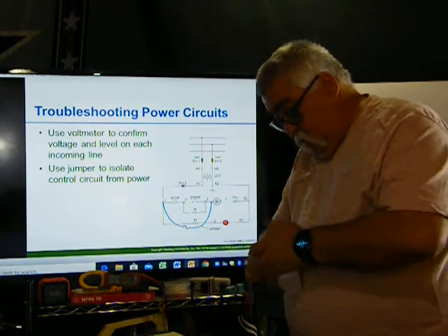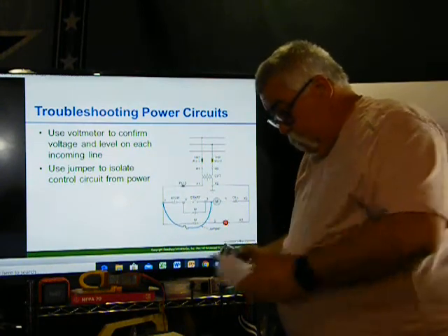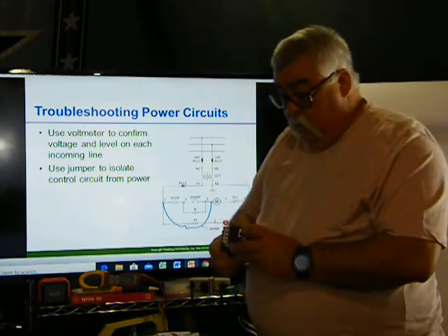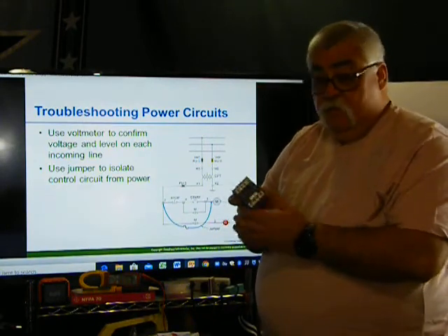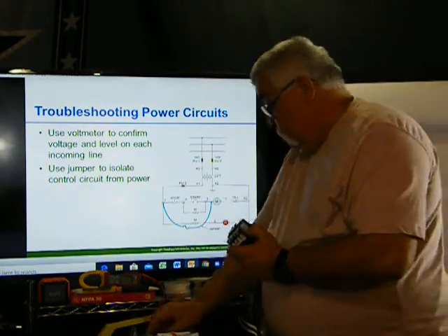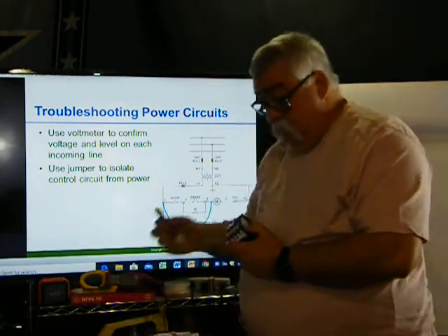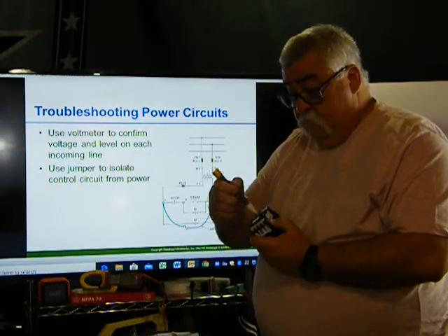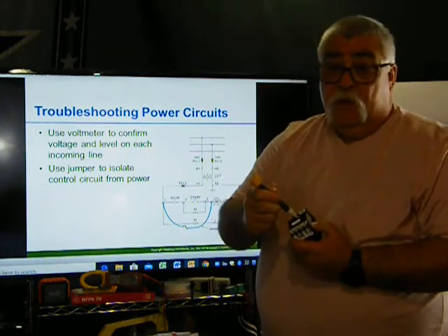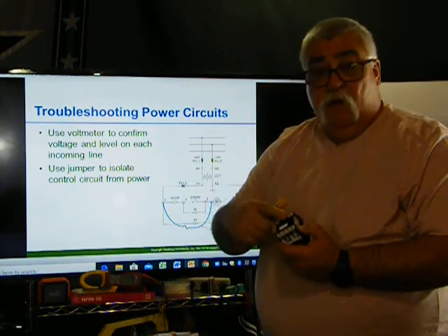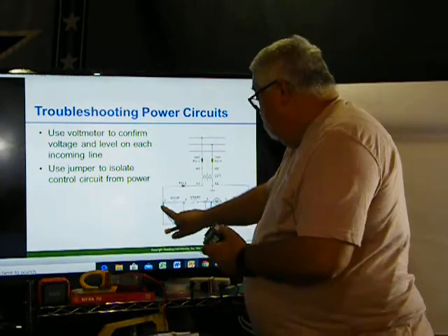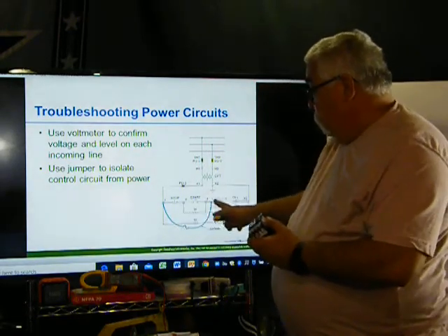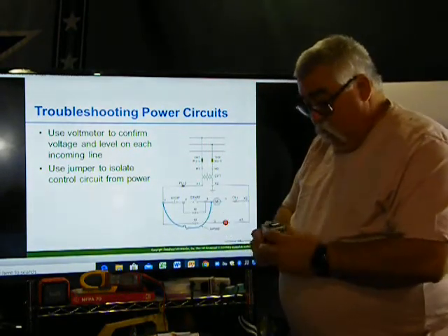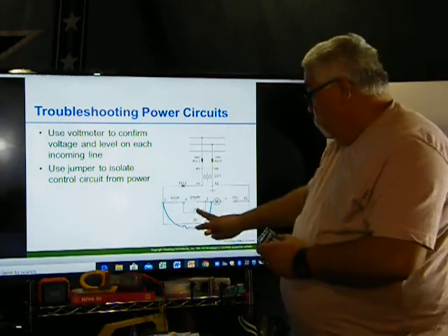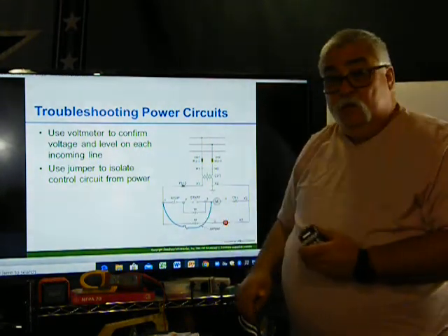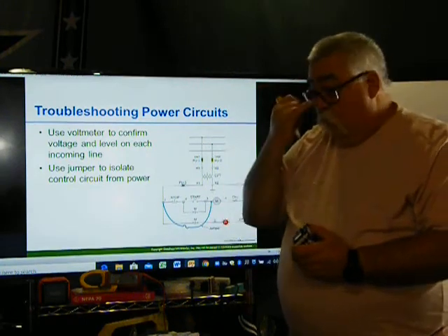My big contactors, contactors are at school. I do have these little ones. Okay, this part right here in the center. Get something, push it in. If it closes and the motor comes on, then we know where a problem may be. So it may be somewhere in these stop starts, these start switches, or the contactor, the auxiliary contact is not closing and holding. So that's one of the things that we have to check.